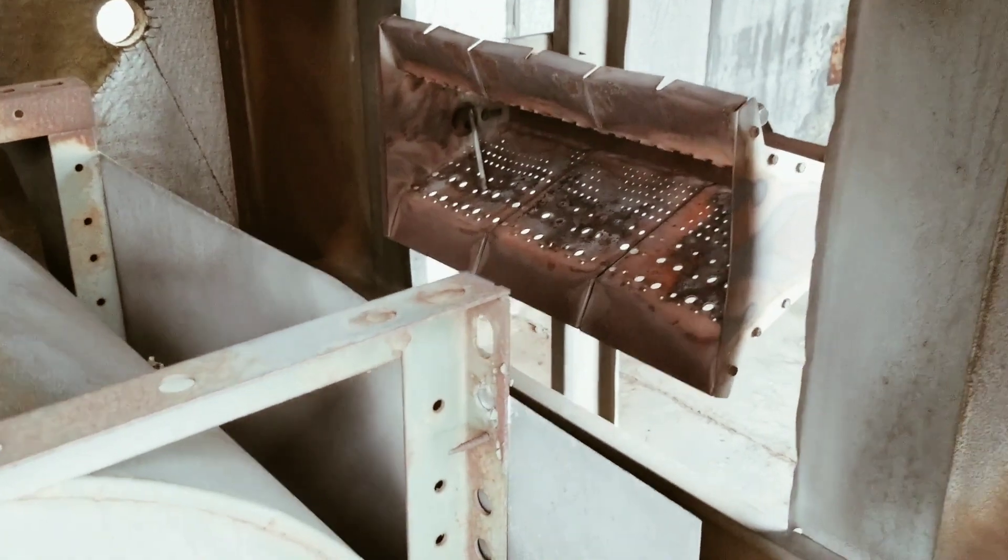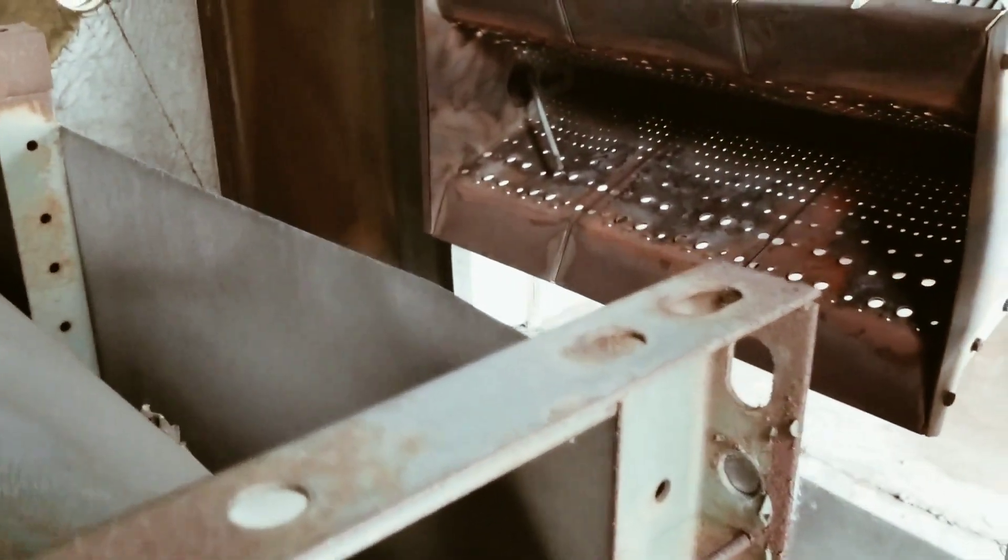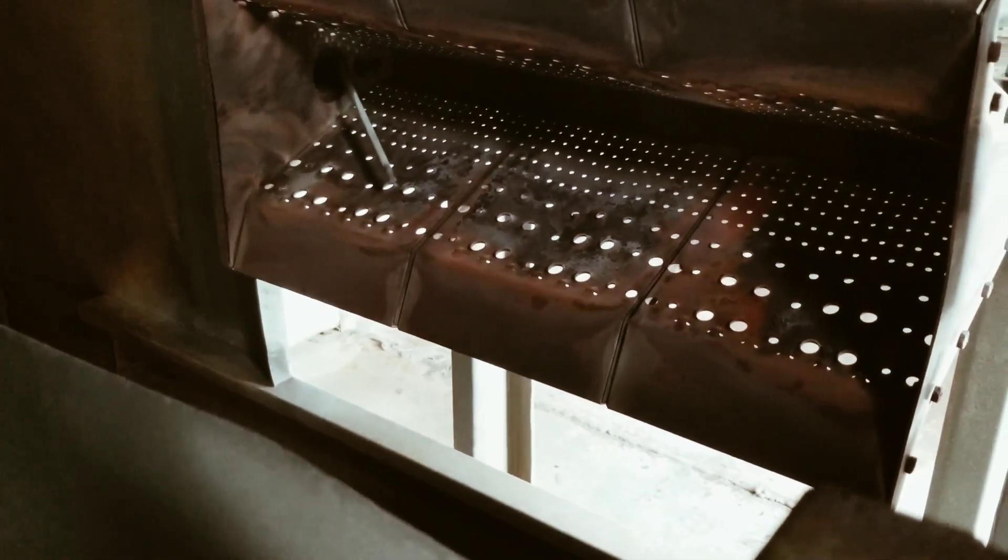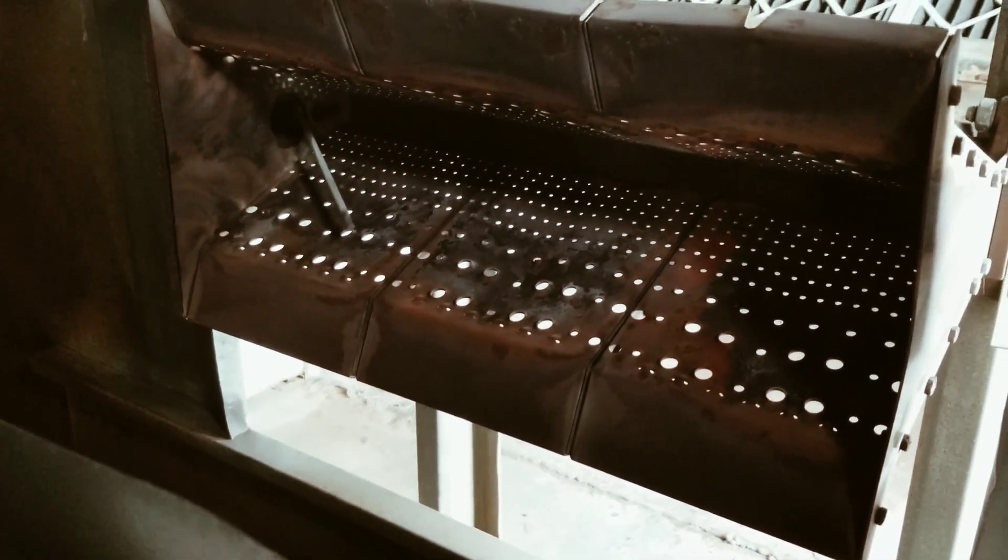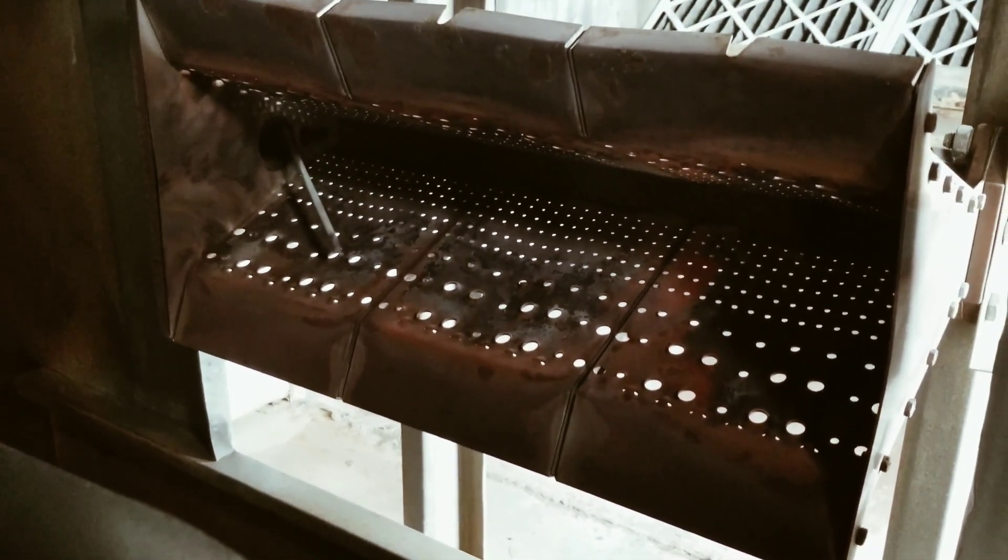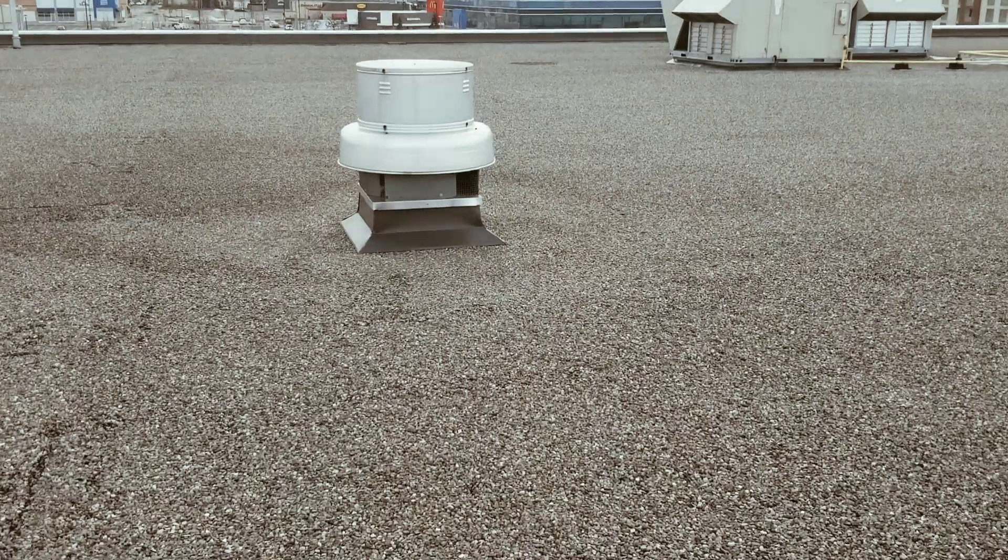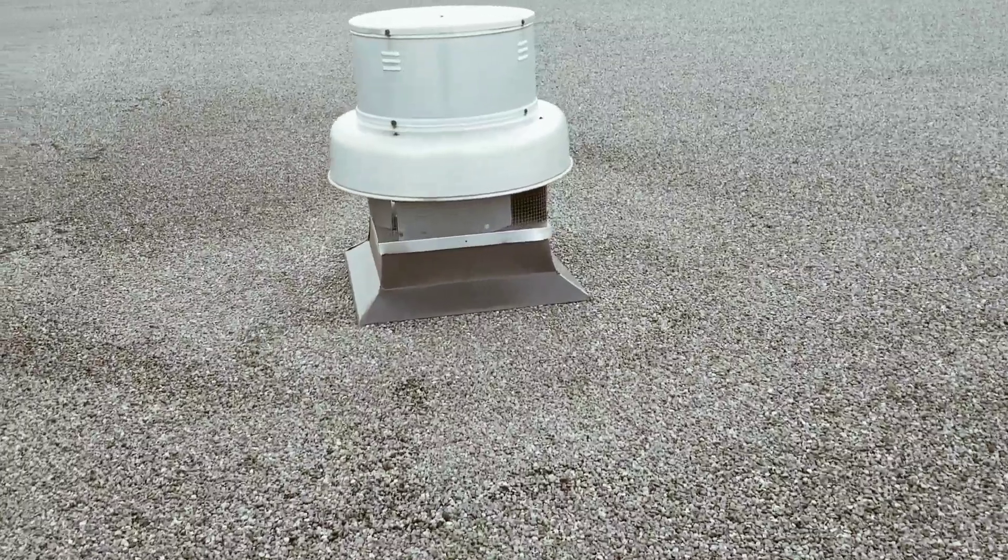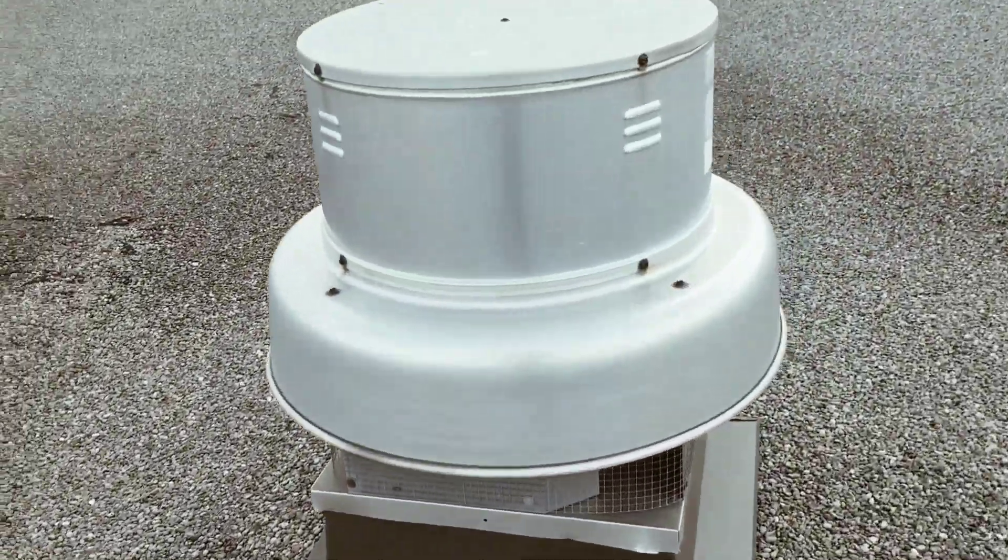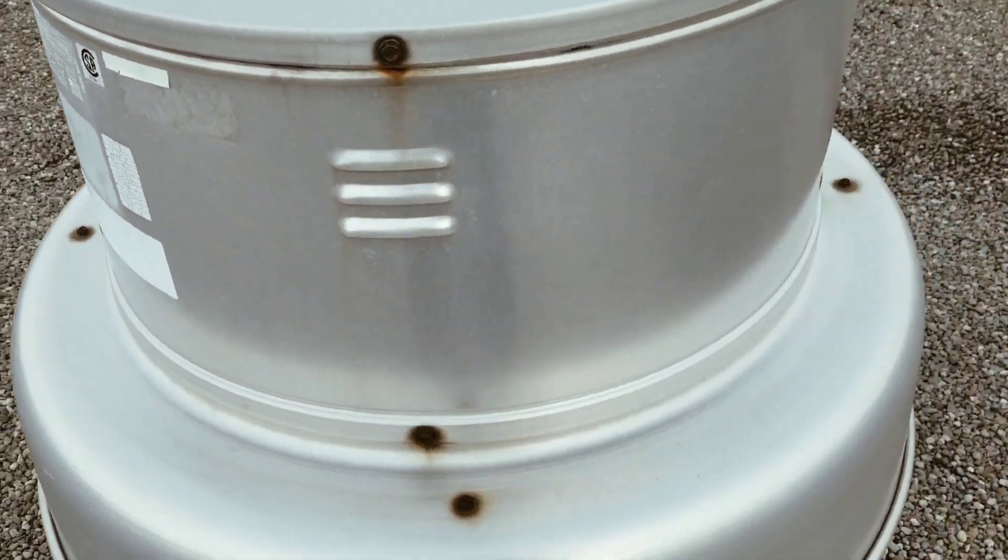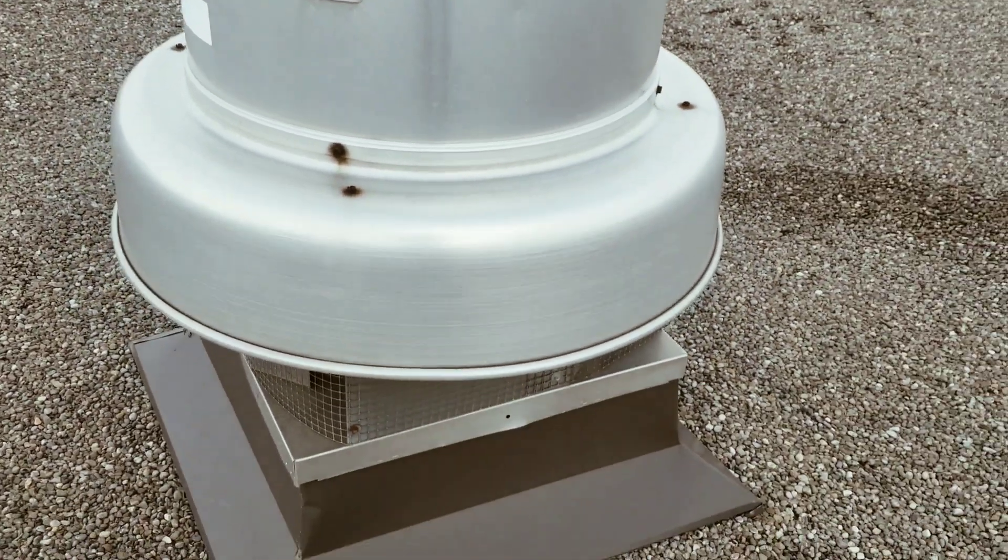There are exhaust fans that have to be tied in conjunction when using a direct fired makeup air, and I'll show you those exhaust fans. They have to be mechanically hardwired in so that this thing can't start up if the exhaust fans aren't running. There are three of these fans tied in in conjunction with the direct fired makeup air.